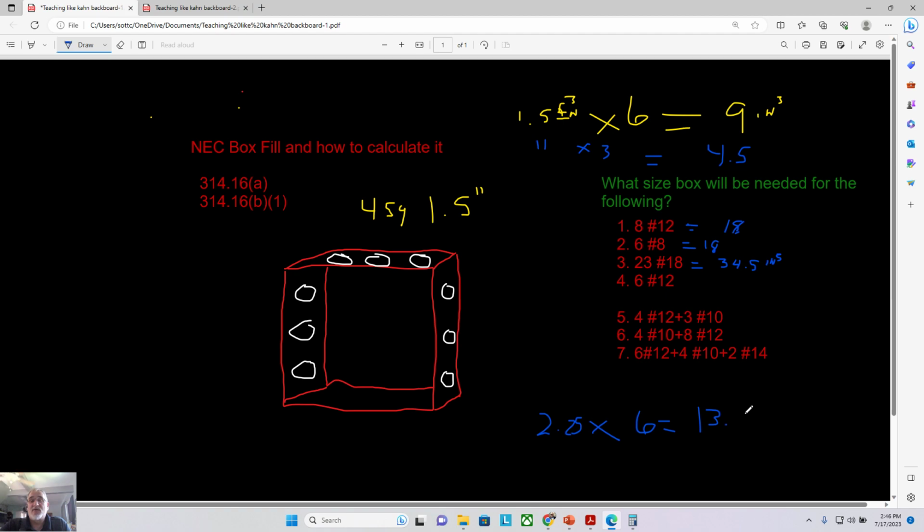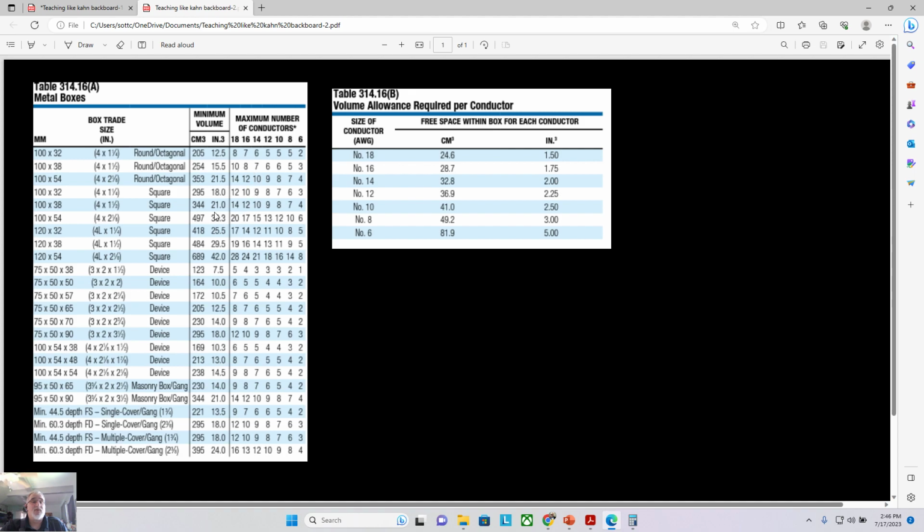Just like at the whiteboard, I'd be erasing stuff as I do it because I make mistakes like I'm standing there, and much more with this mouse. So you guys bear with me. So this guy right here is going to have 13.5 cubic inches required for it. For 13.5, we can go with one of our simple standard 1.25 inch deep 4 square boxes.